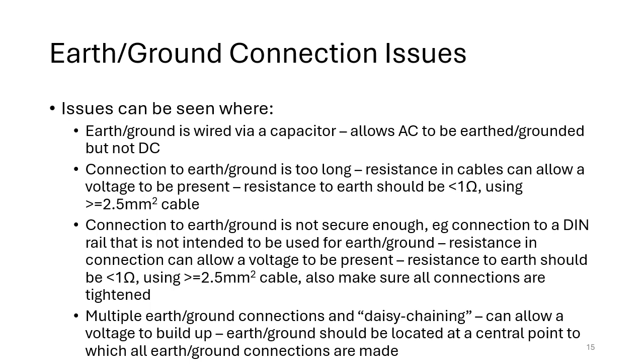And interestingly, we talk about earth or ground. People say, well, what is the earth or ground? It is literally a connection into the earth or ground. So I've seen this where if the connection to the ground is poor because it's a longer distance away, one of the things you might do is buy a large physical metal spike and you bang it into the ground. It's quite a large spike, maybe a meter long, but you hit it into the ground, and that gives your earth connection back into the earth, so your earth acts as your safety conductor. So that's another way of doing it, is actually provide a new earth or ground connection, and then provide your local safety signals into that physical earth or ground protection.